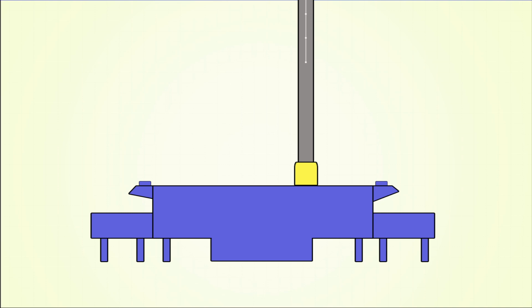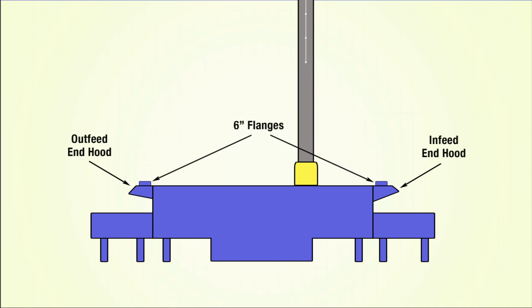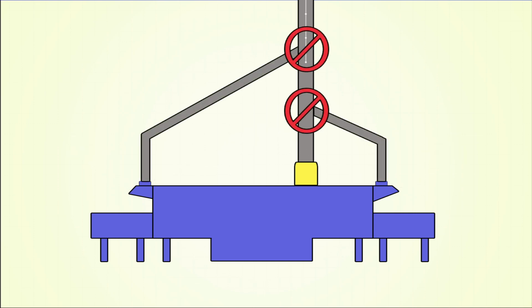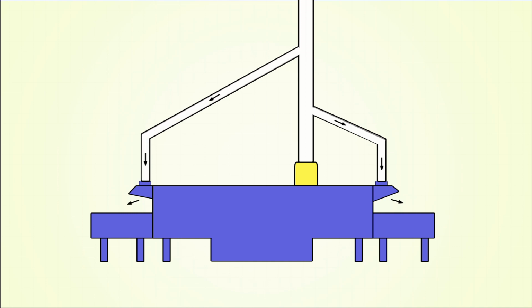unit through the ceiling. Some M&R gas dryers have end hoods at the infeed and outfeed of the dryer. These hoods have a 6-inch diameter flange on them. These are provided in case a customer would like to add additional exhaust ducting. These end hoods and the ducting associated with them must never be tied into the main exhaust blower on the dryer. The result is that the air being exhausted through the main exhaust duct will then be rerouted down to the end hoods and blown out to the infeed and outfeed.